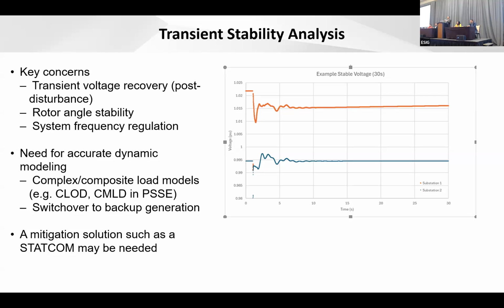But if you're talking about low load scenarios, your voltages are already high, and say you're losing 1 gigawatt, 2 gigawatts of load suddenly, you can expect even higher voltages. You can even have frequency events. So you really need to study all these scenarios—it has to be a very comprehensive analysis.